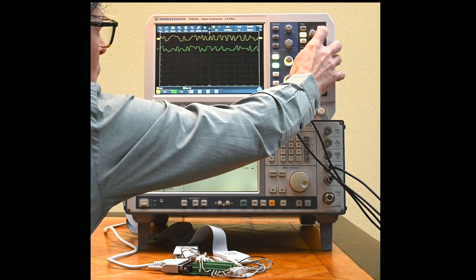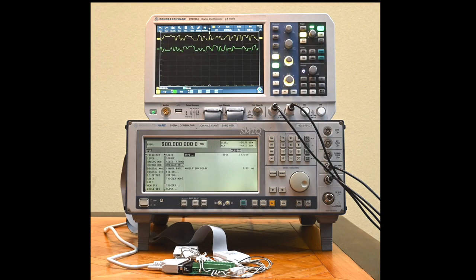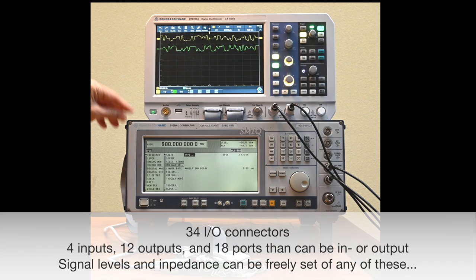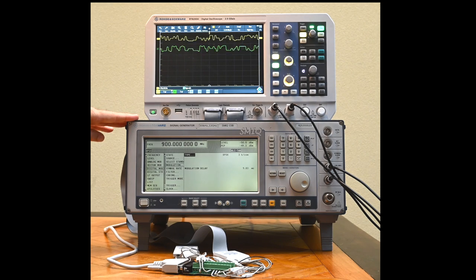The thing is, if I got this on continuous on my scope, I don't have any syncing going on. Now, I can solve that basically thanks to the quite generous number of in-out type of ports on this device. I was quite impressed. Actually, I was doing a little count, and this device has a total of 34 in-outs for things like sync and clock and triggering and data, etc. Even in the standard version, it becomes more if you install additional options like bit error checking and fading and that type of stuff. So 34 I/O connectors, some of them input, some of them output, most of them switchable between input and output. And I'm not even considering the serial port and the IEEE port, I think for software update, etc. Really the type of technical I/O signals.